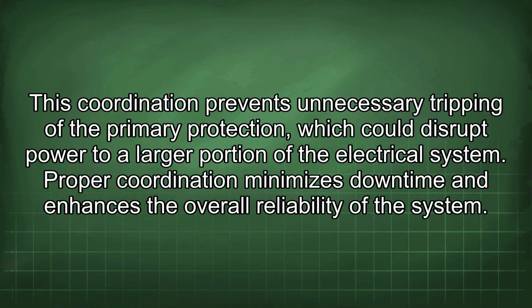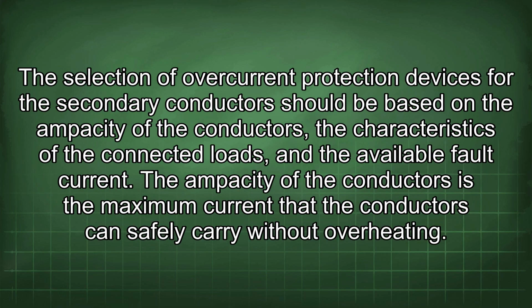Proper coordination minimizes downtime and enhances the overall reliability of the system. The selection of overcurrent protection devices for the secondary conductors should be based on the ampacity of the conductors, the characteristics of the connected loads, and the available fault current. The ampacity of the conductors is the maximum current that the conductors can safely carry without overheating.